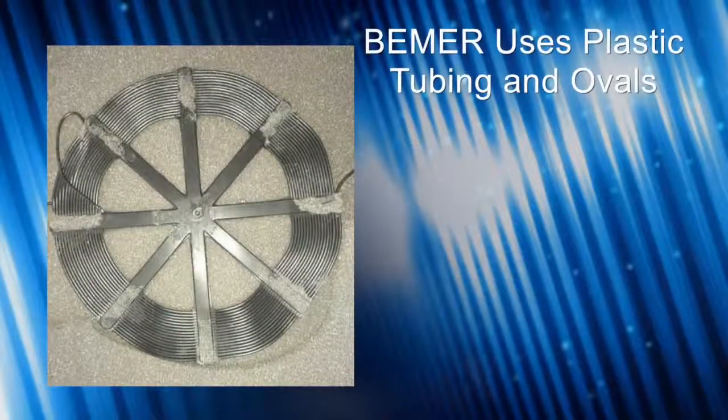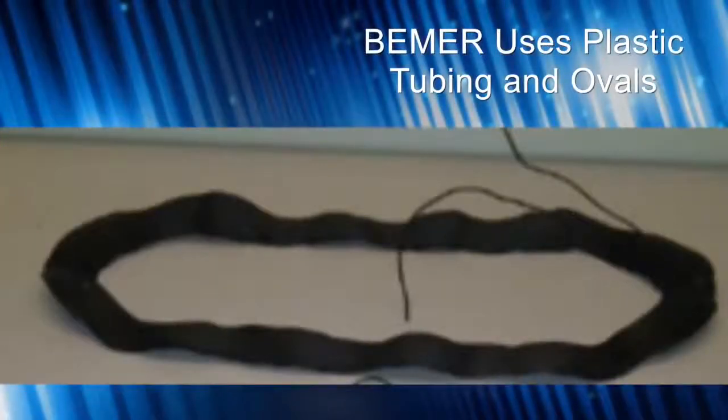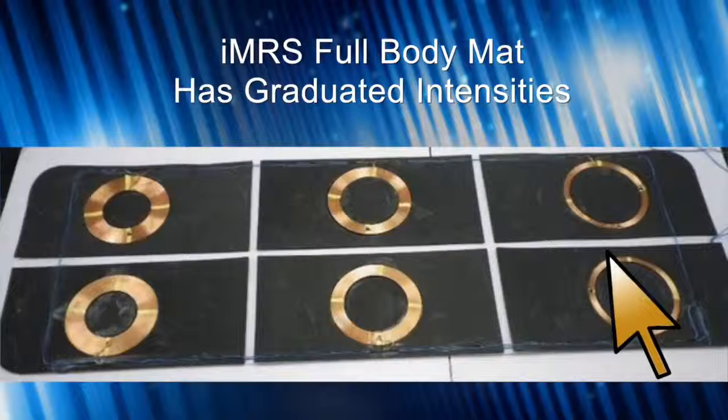The BEMER uses plastic tubing with spacing between consecutive turns, and even oval geometries in the leg area of the full body mat and the B-pad. The B-spot does use a perfectly circular ring, but only three turns in the coil. The IMRS full body mat also has a graduated intensity: the head and neck and thyroid are very sensitive, so the design puts most energy at the feet, middle intensity at the torso, and lower intensity at the head, so you can maximize energy without triggering reactions.